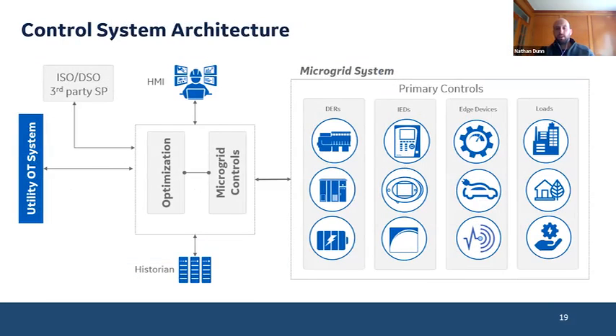Here's an example control system architecture a typical system may have. You have the utility system at the highest level, maybe their DMS or ADMS. You could even have the ISO or external markets communicating into the optimization engine, our tertiary controller, which talks down to the microgrid controller, which connects out to all the primary assets. How these controllers work together, and the communication style chosen, really drives the outcomes our customer is looking for.